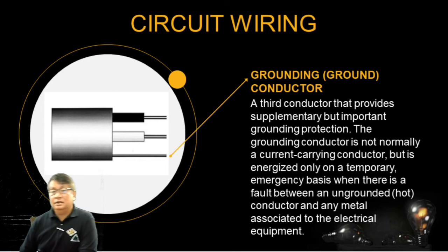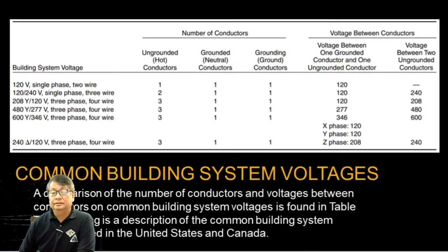And then a third conductor that provides grounding, a supplementary but important grounding protection. The grounding conductor is not normally a current carrying conductor, but is energized only on a temporary emergency basis when there is a fault between an ungrounded hot conductor and any metal associated with the electrical equipment. Okay, so we have these common building system voltages.